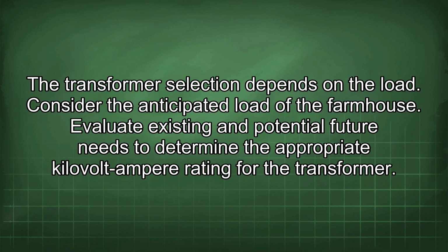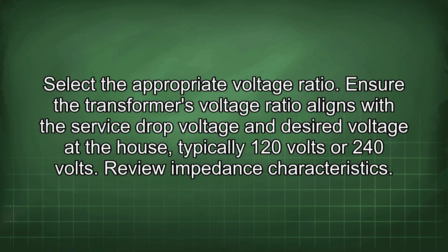The transformer selection depends on the load. Consider the anticipated load of the farmhouse. Evaluate existing and potential future needs to determine the appropriate kilovolt-ampere rating for the transformer. Select the appropriate voltage ratio. Ensure the transformer's voltage ratio aligns with the service drop voltage and desired voltage at the house, typically 120 volts or 240 volts.